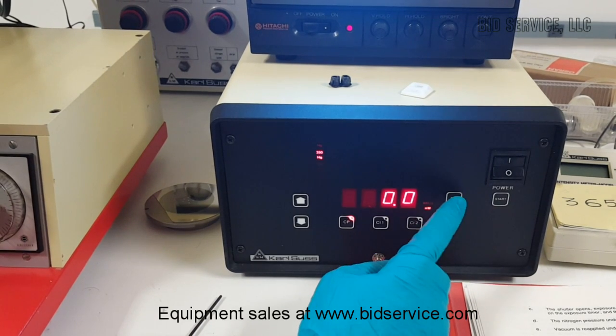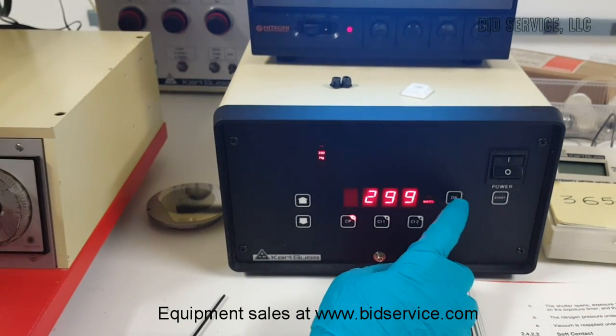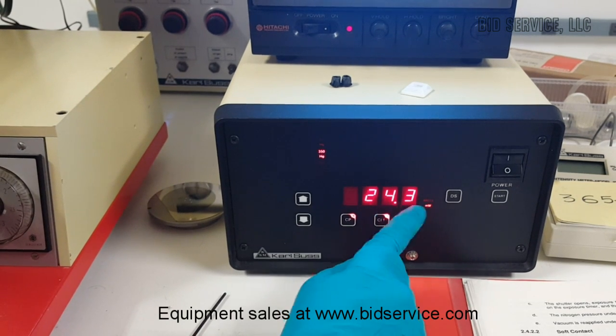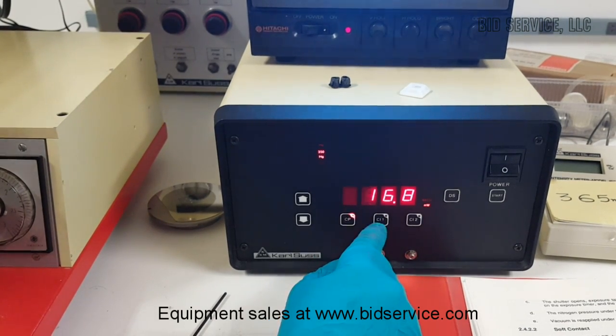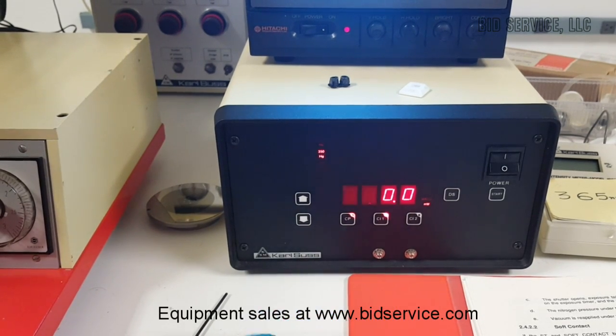There is a dual detector inside the system. When the shutter is open, I am able to see the reading. At this moment, the power is still controlled in constant power mode, and I can see the UV radiation energy. By pressing D a second time, we can see the energy level at 405 nm.